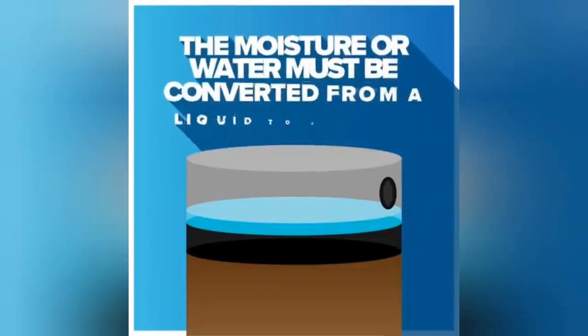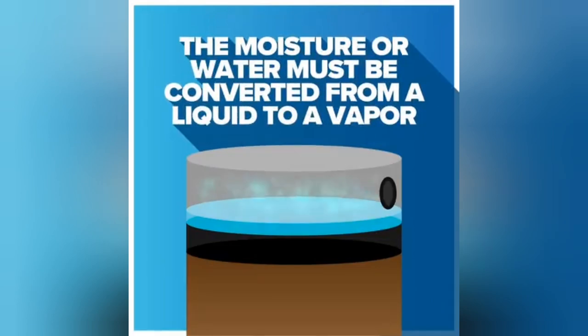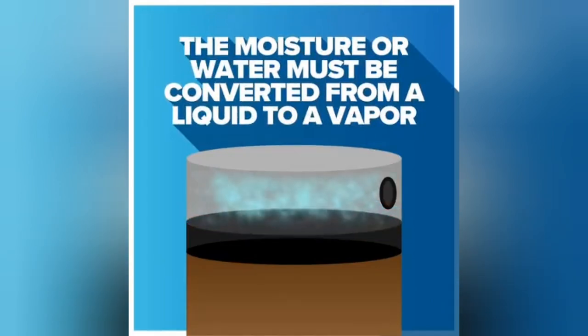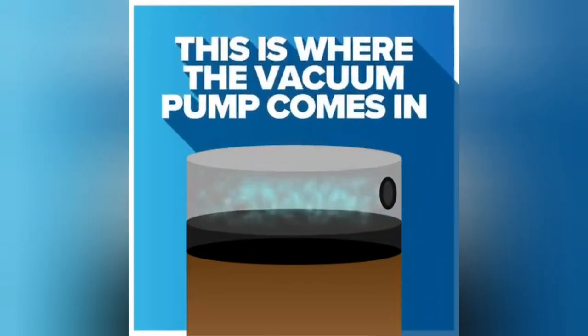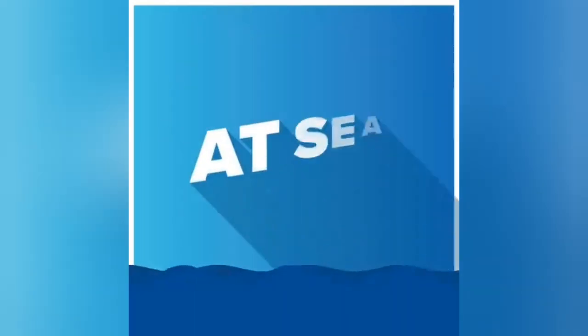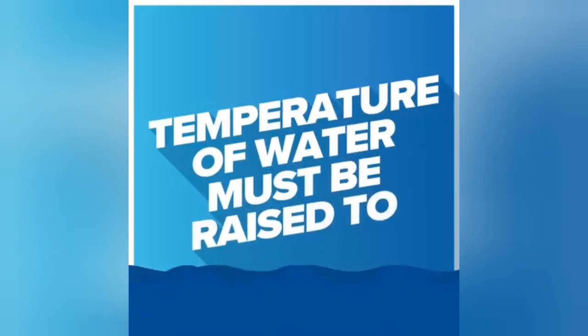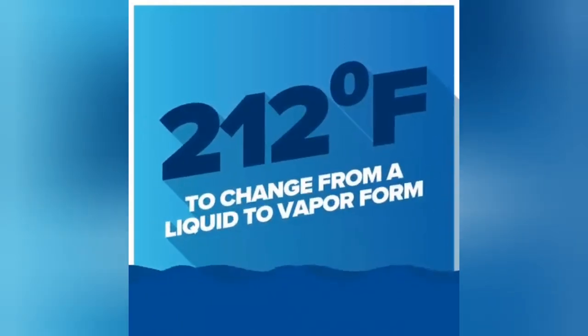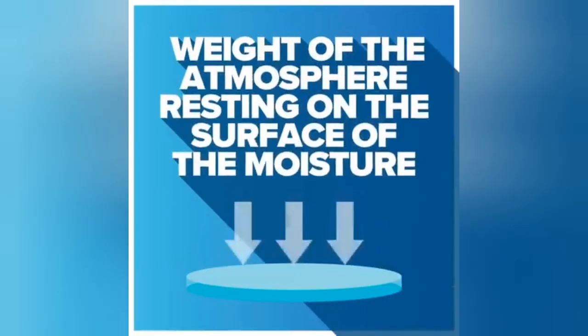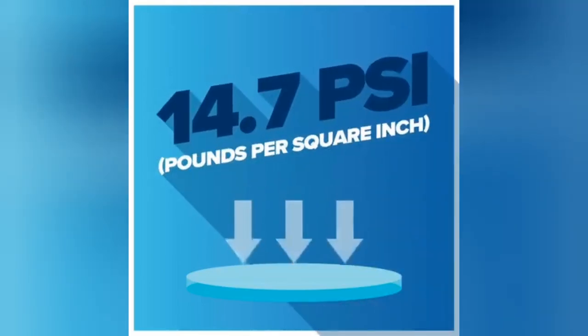The moisture or water must be converted from a liquid to a vapor before it can be drawn out of the system. This is where the vacuum pump comes in. At sea level, the temperature of water must be raised to 212 degrees Fahrenheit to change from a liquid to a vapor. This is due to the weight of the atmosphere resting on the surface of the moisture, which is 14.7 psi bearing down on that moisture.